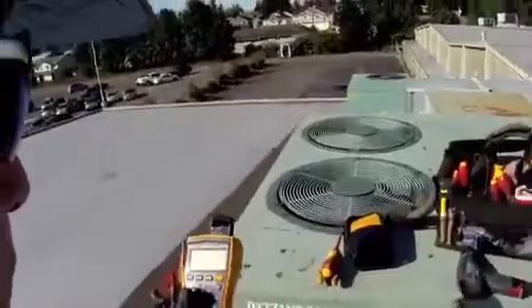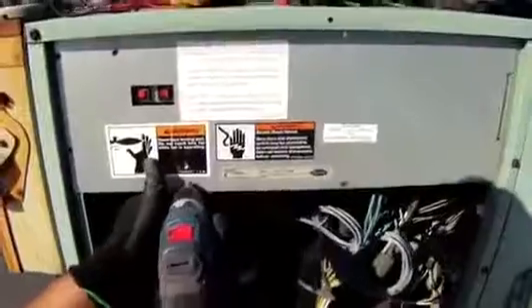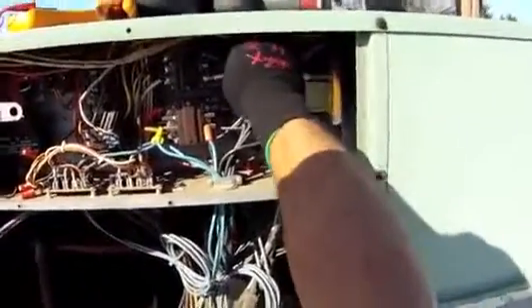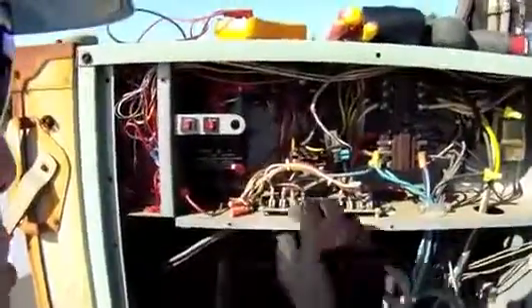We're going to check a capacitor today. It's a pretty simple check, but it's important to have it done correctly. Using safe procedures and the right tools, this simple check can be done quickly and efficiently. I have two compressors right here and an electrical cabinet here. We're going to de-energize our system and open up the electrical cabinet and just take a look in there. Anytime I open up a piece of equipment, I like to look at the electrical. These units sit up on a roof, they're used a lot, and I like to go through and check all my wiring.